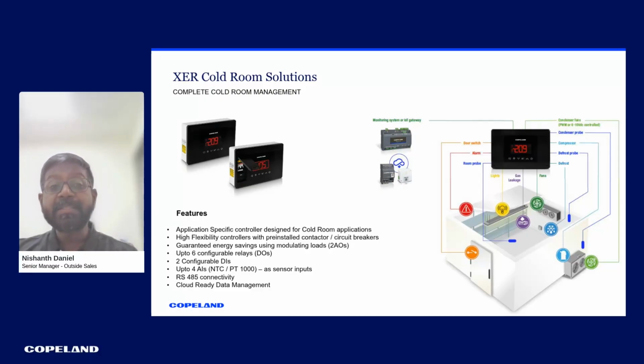This will also give you enhanced energy savings as it has a lot of AO points, which are analog output points, used for modulation of energy. They have up to 6 configurable relays and 2 configurable digital inputs for getting the digital alarms onto the controller. These controllers also support around 4 analog inputs: the room sensor, the evaporator for defrost applications, the condenser for monitoring, and ambient. These controllers also come with RS485 connectivity, which means up to 32 controllers can be networked at a time, and then looped in to a master controller or a supervisory controller.